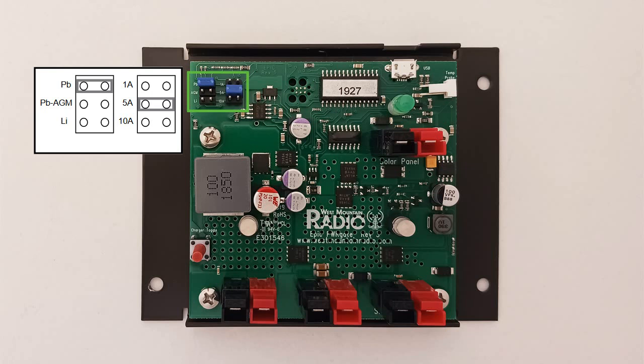Remove the case screws to access the internal jumpers. Select the correct chemistry and maximum charge current. Sealed lead-acid gel batteries and sealed lead-acid absorbed glass mat (AGM) batteries usually have a maximum charge current that is 10% of the amp-hour rating.